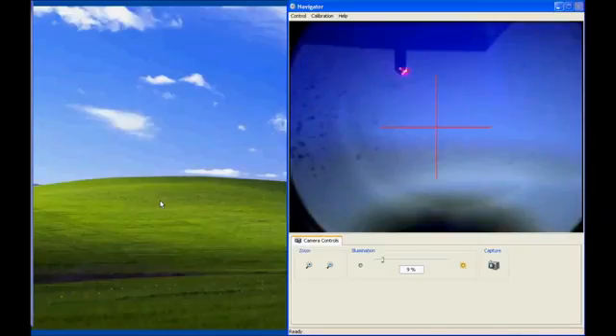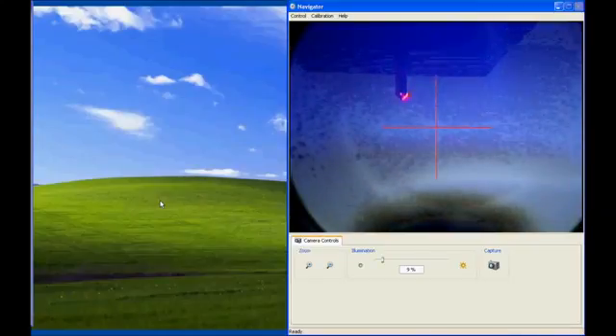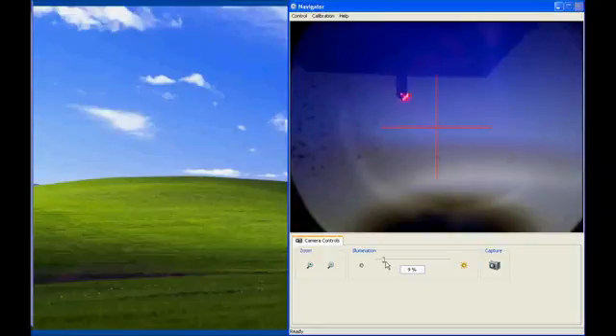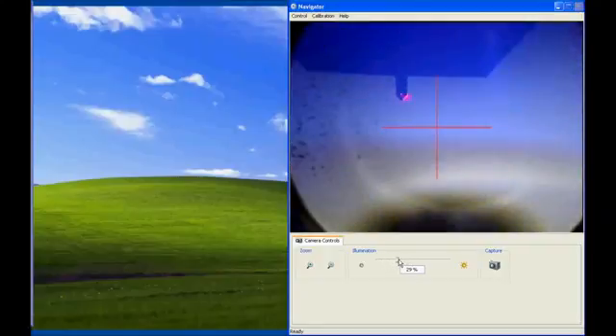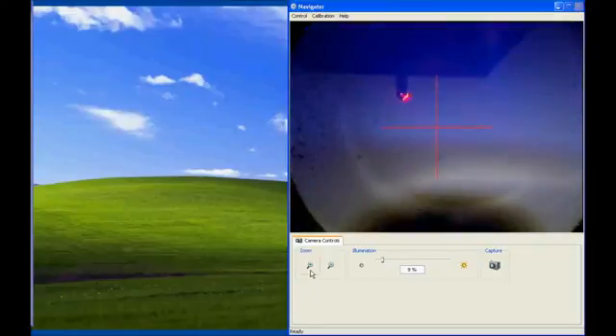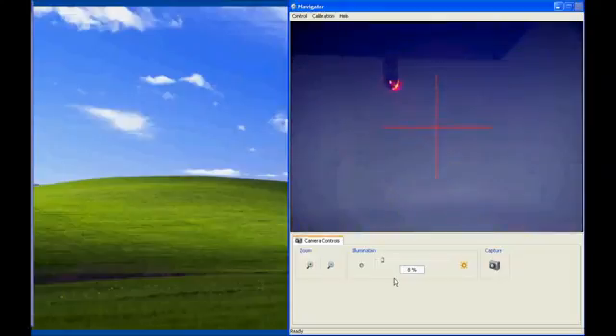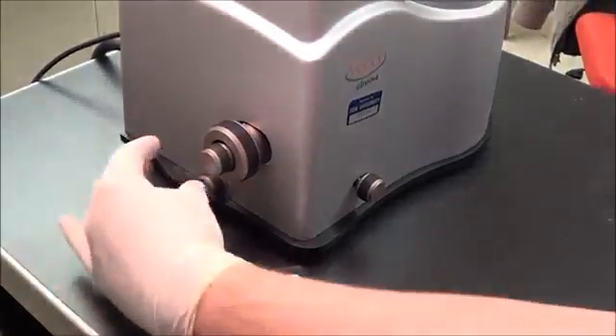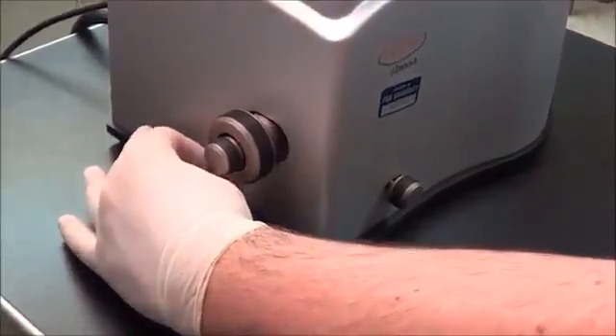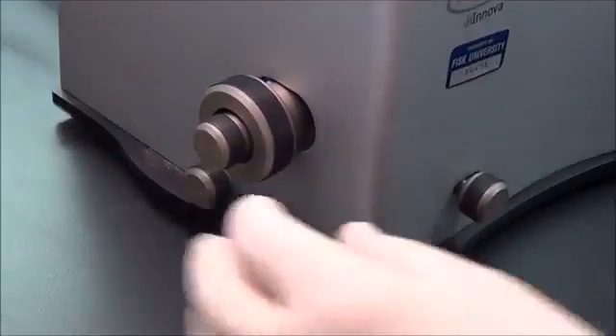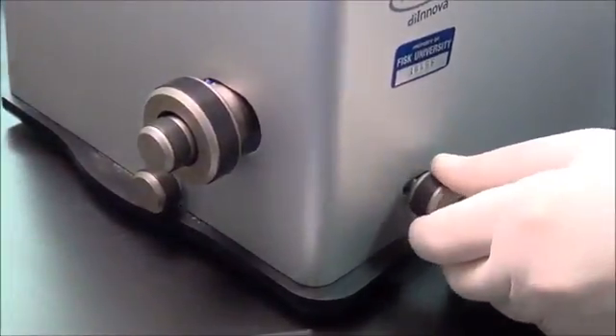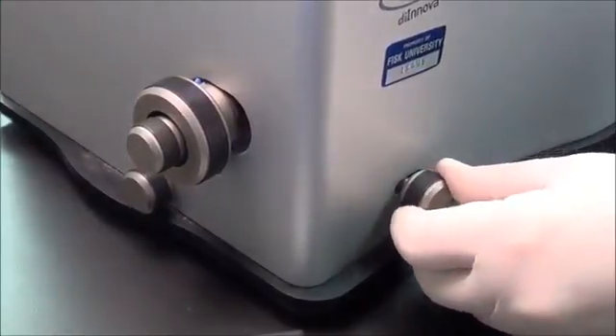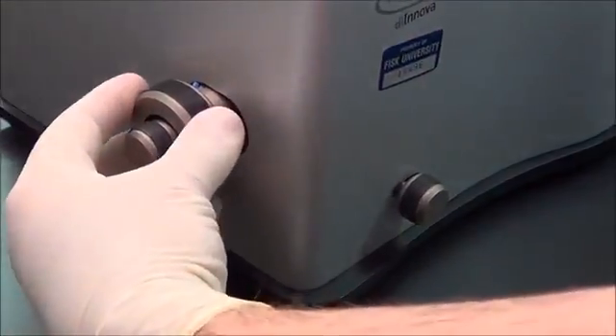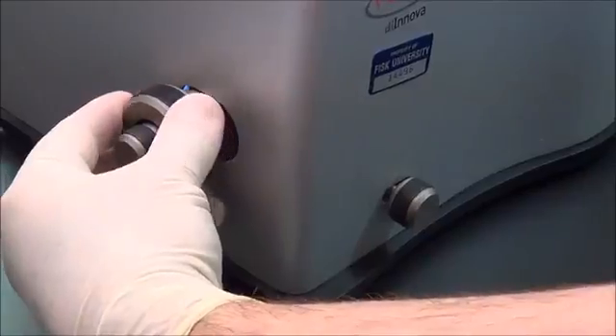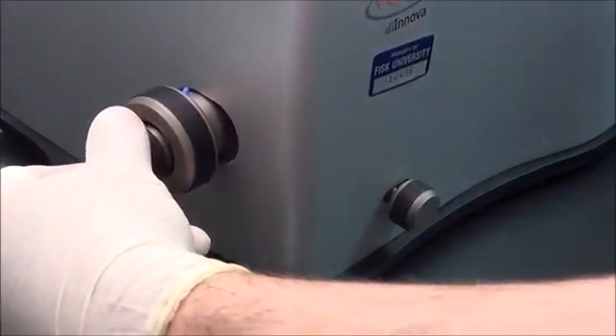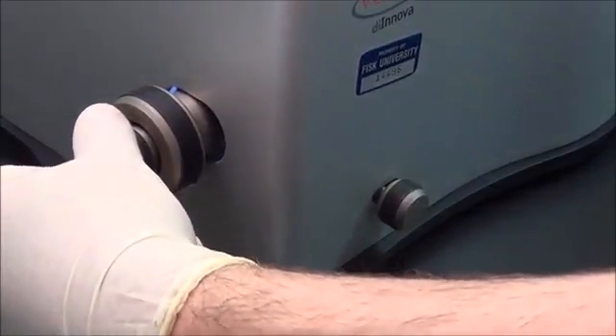On our right screen is our microscope video feed. This slider controls the illumination of the sample. And we can zoom in and out with these icons. The bottom knobs on the AFM control the positioning of the microscope. The side knob is the vertical control, while the front knob is the horizontal control. The upper knob on the side controls the focus of the microscope, with the larger ring for coarse and the smaller ring for fine focus.